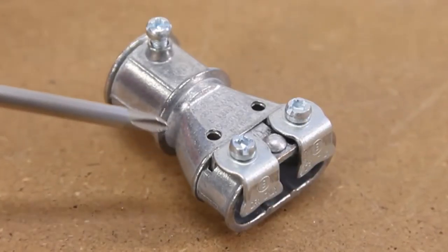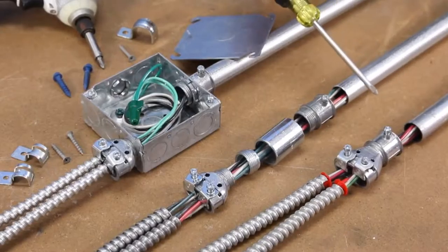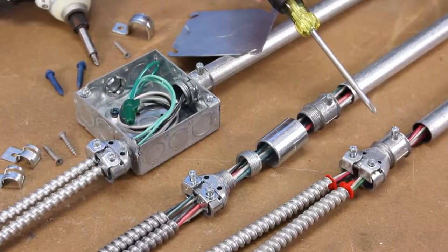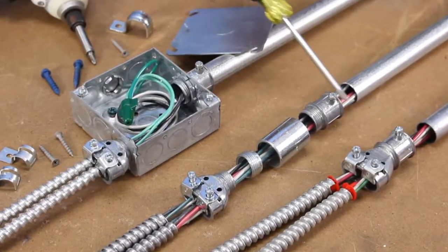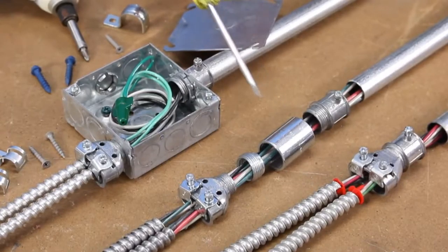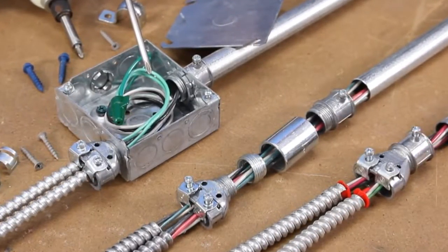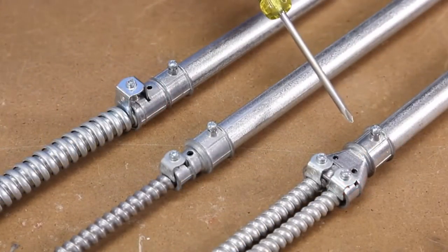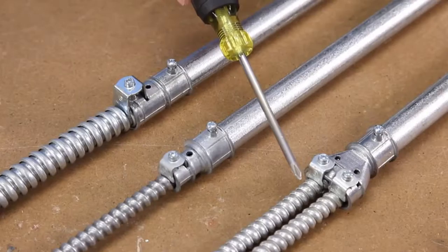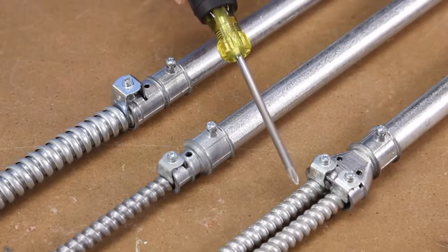The one-piece design promotes a quick installation. Bridgeport's 4157-DC gives you a UL-listed 10-15 minute quick installation compared to the assembly of fittings with a three-quarter inch rigid coupling or the labor and material intensive one-hour junction box installation. The duplex 4157-DC has an MC cable range of 14-2 to 10-3 and 3/8 inch flexible metal conduit.